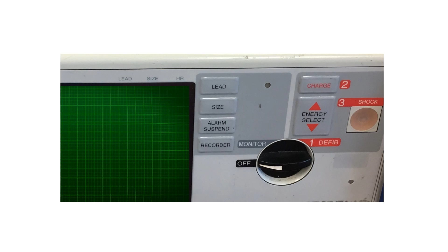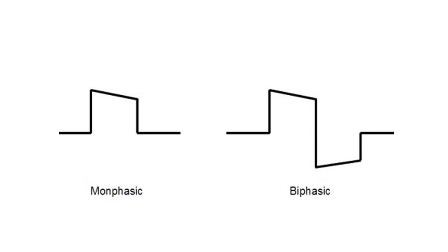There are controls to select the energy level, which is usually expressed in joules. Energy levels range from 5 joules to 360 joules for a monophasic defibrillator, while it ranges from 2 joules to 200 joules for a usual biphasic defibrillator. Monophasic defibrillators deliver a unidirectional pulse of energy, while the biphasic defibrillator reverses the polarity of the current after the initial phase. Biphasic defibrillation is more effective and requires only lower energy.